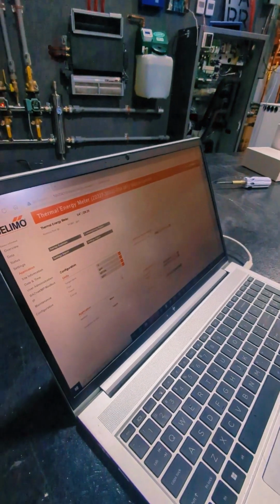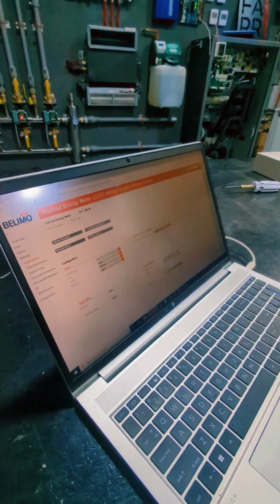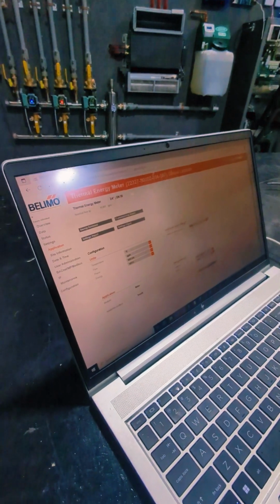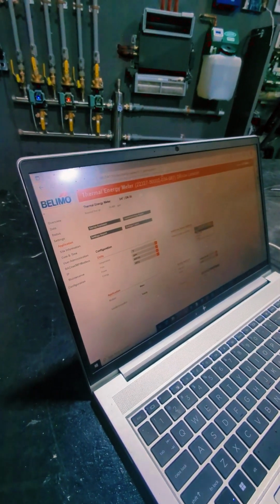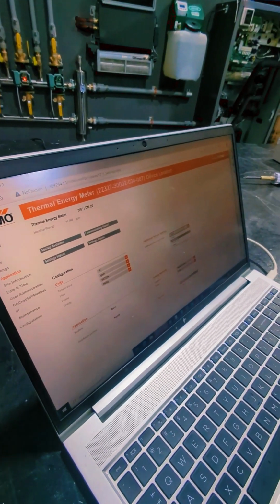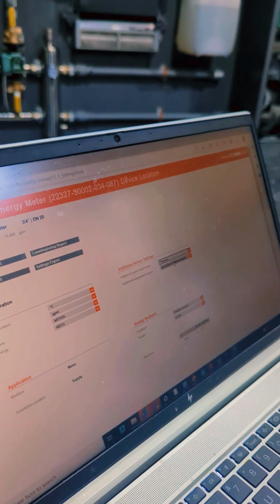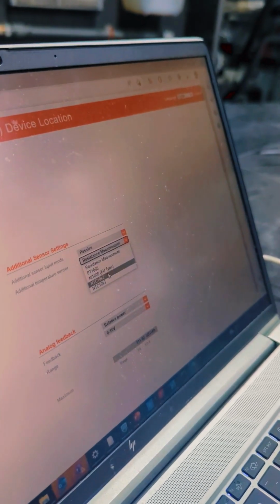Okay. So where I'm going is to this sub menu that says additional sensor settings. I'm going to pull down this menu and I've got three options: active volt, passive, or switch. And because this is a passive sensor, it's a 10K Type 3 thermistor, I will choose passive. And in a moment, I should see a second one. So it says resistive measurement. So I've got options for PT1000, NI1000, NTC Type 2, or 10K Type 3. So I'm going to use 10K Type 3 because that's what we have.